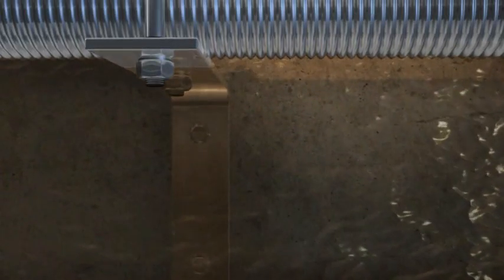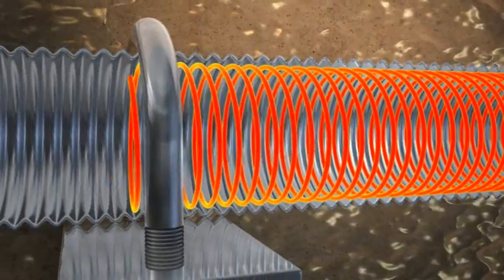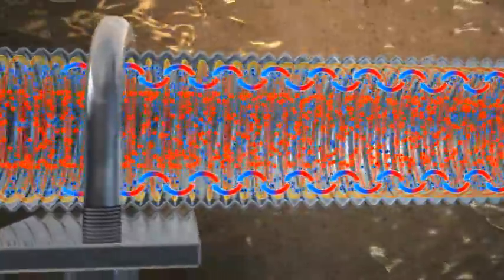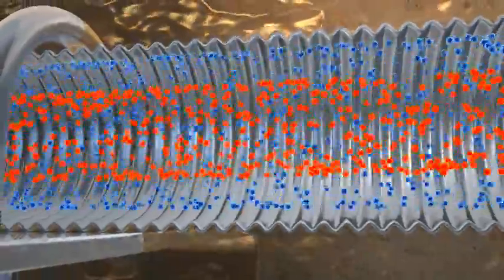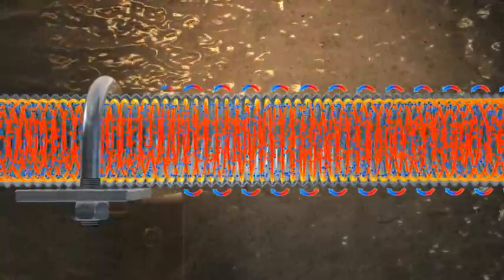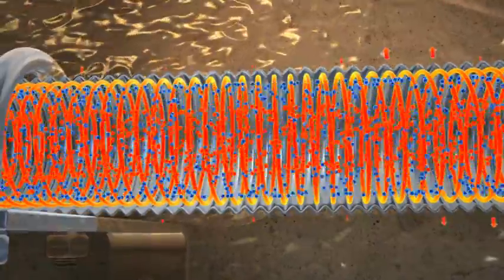The helical shape of the pipe's corrugation is of further advantage over conventional smooth-walled pipes. It swirls the hot water around as it flows through the pipe to create a turbulent flow. This method exchanges the warm water at the center of the pipe with the somewhat colder water at the periphery, to transfer an optimum temperature to the substrate. Thus, the substrate is slowly heated to the required process temperature.